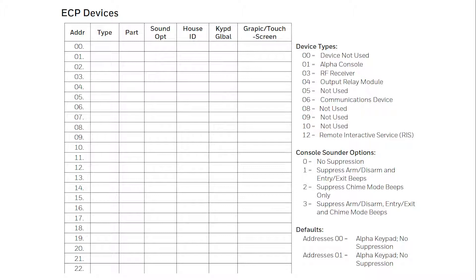Press 1 for yes. Enter the address number you set the DIP switches for on your 4204, then press star. Enter device type 04 for output relay module, then press star. Enter device address 00 star to quit this menu, but when asked to quit menu mode yes or no, press 0 for no. The panel now knows that it has a relay or relays connected, but it doesn't know how they will be activated.